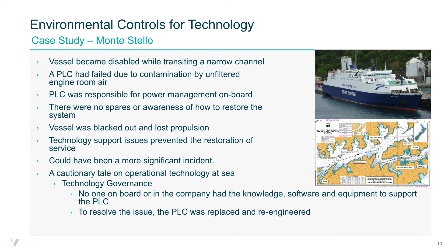Now that was really just one of the issues identified as part of the problem. When the repair was attempted, it was discovered that no one on board the vessel, or in fact in the company, had knowledge of the software and the equipment to support that PLC. To restore the vessel to service, the PLC actually had to be replaced. They had to re-engineer the solution because no one had the ability to reload the software, and I don't believe there was an offline copy of the software running that critical system on board. So they essentially had to tear the whole system out and replace it to make the ship operational again.